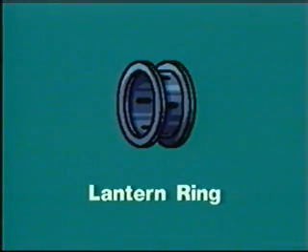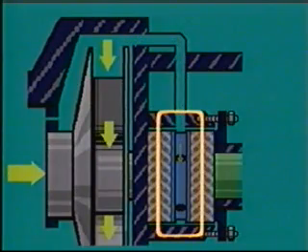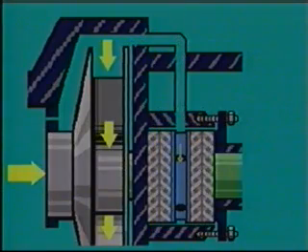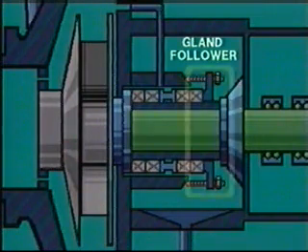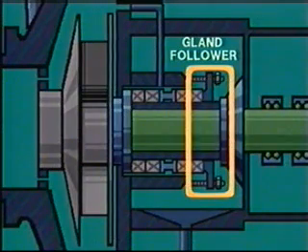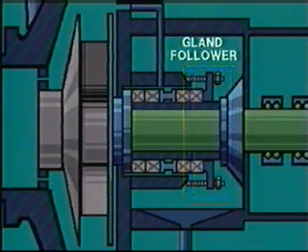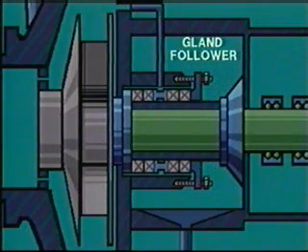Lantern rings are sometimes used to pressure lubricate the packing. These perforated metal rings are located between layers of packing in the stuffing box. They allow additional fluid from the gland sealing line to be injected into the stuffing box. That helps lubricate the packing. Look closely and you'll see that this piece called a gland follower fits into the open end of the stuffing box. It holds the packing and lantern ring in place against the throat bushing. If you adjust the gland follower's pressure against the other parts of the packing gland, you can regulate the flow and leakage rate of the fluid lubricant.